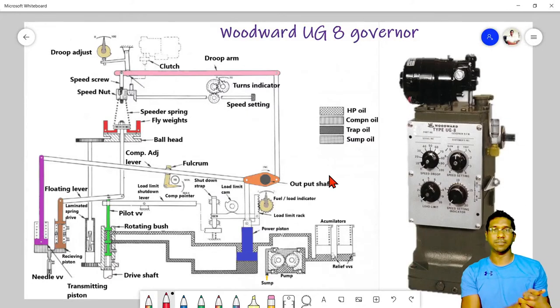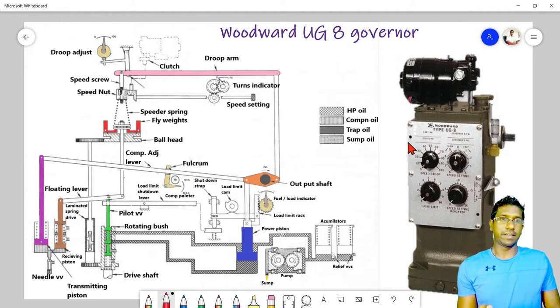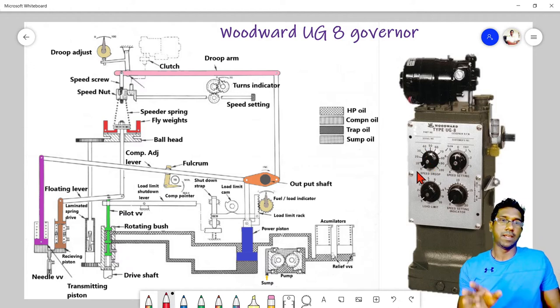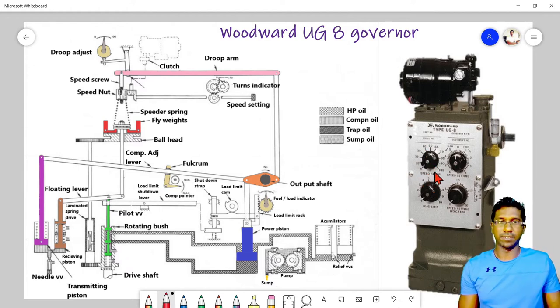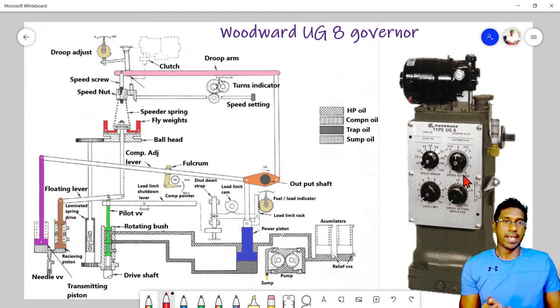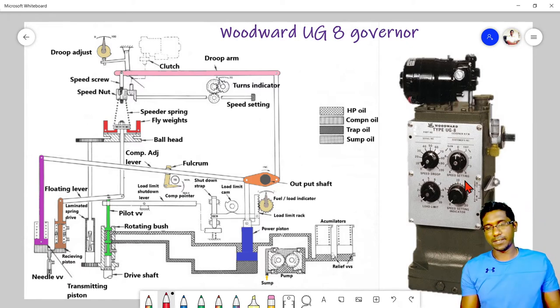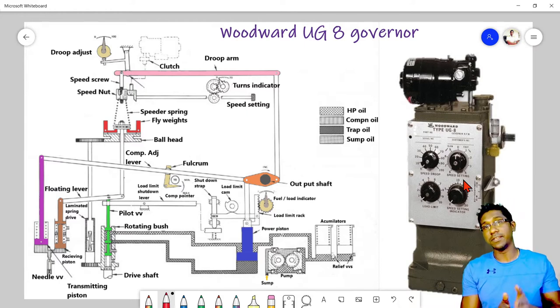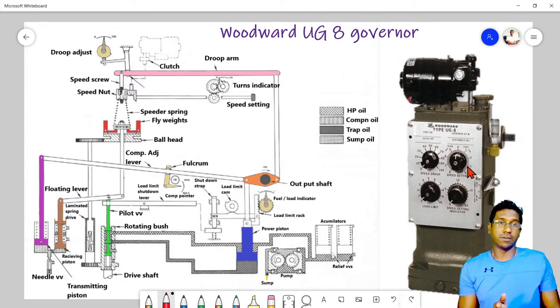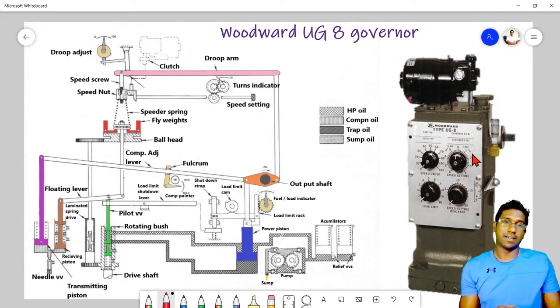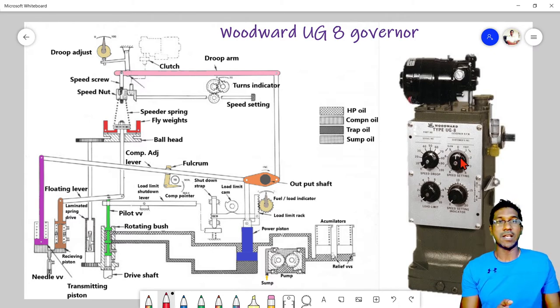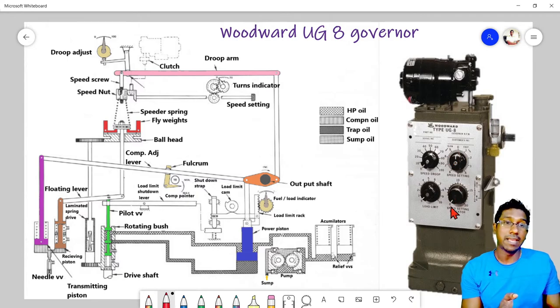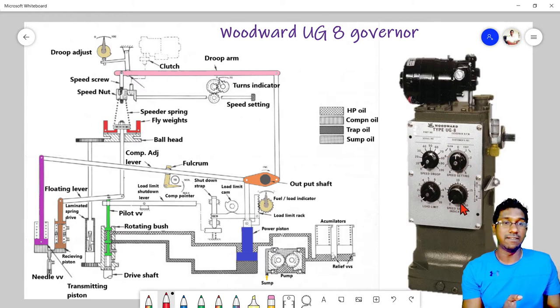Moving back to the diagram: the first dial is for speed droop adjustment. For generator paralleling we need to adjust droop, so this is the knob for adjusting droop. Next is the speed setting knob — the local speed setting knob. Turning it clockwise raises engine speed; turning it anti-clockwise lowers speed. You can turn it up to 20 turns, and there is an indicator below that counts each full turn up to 20.